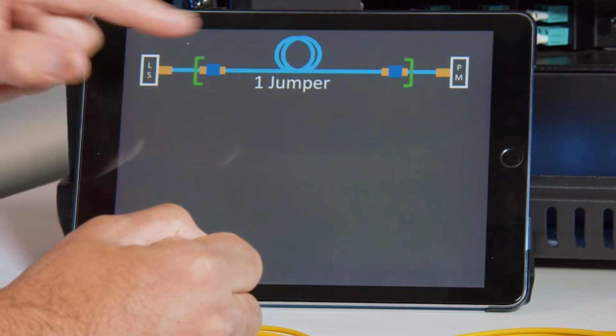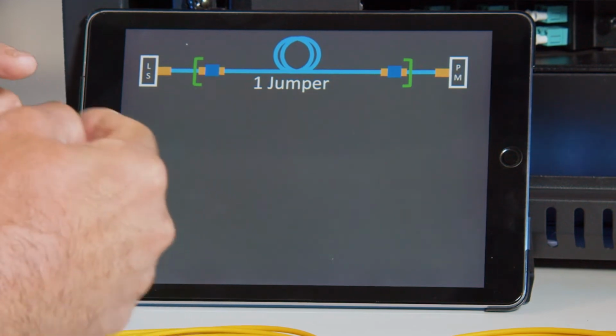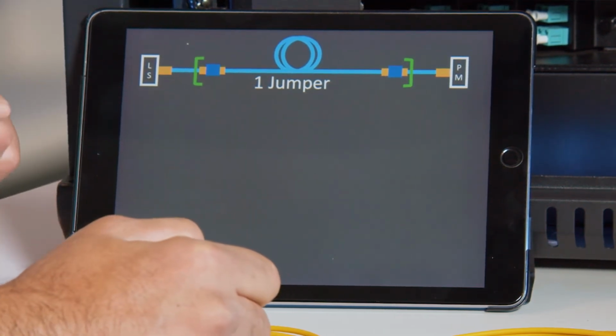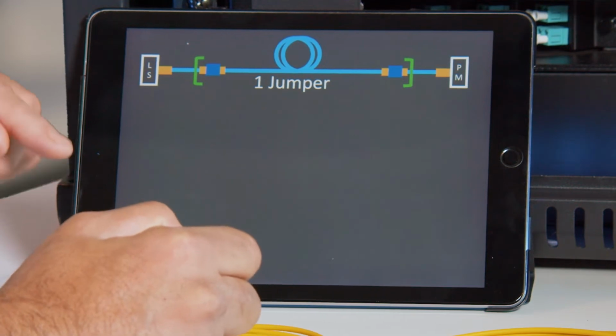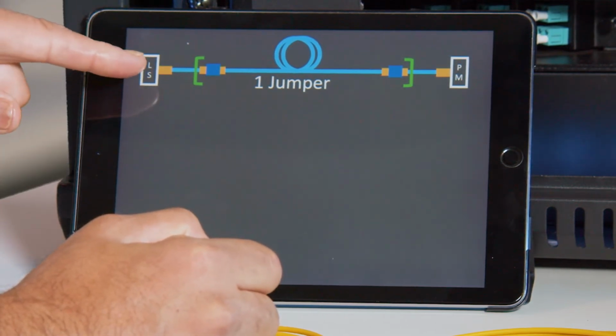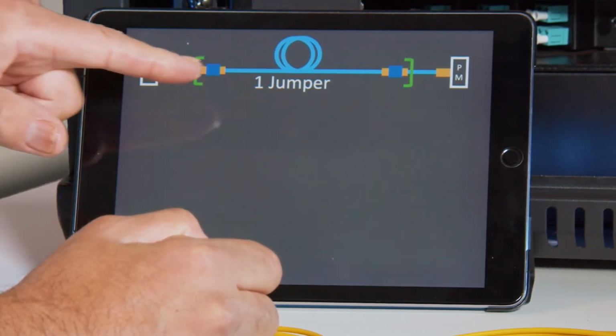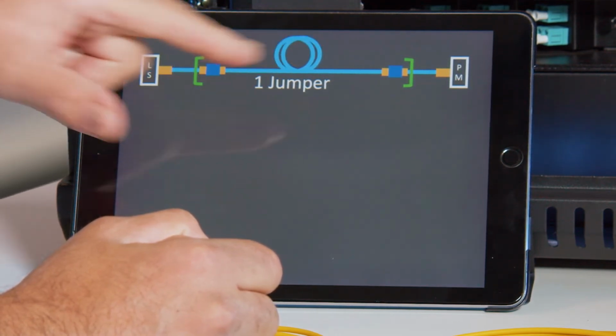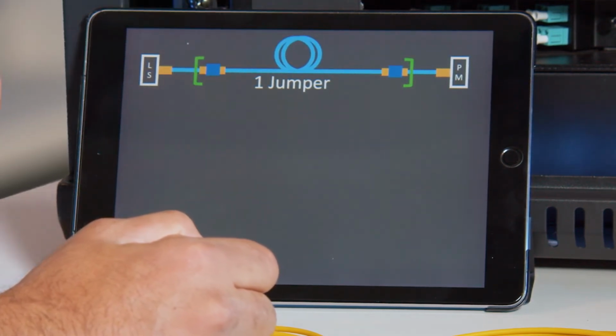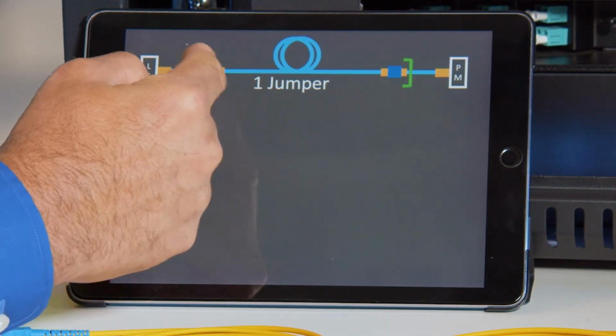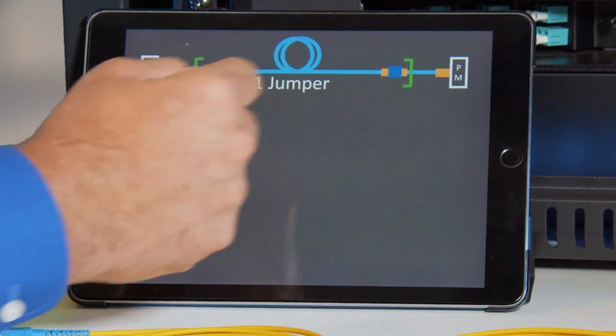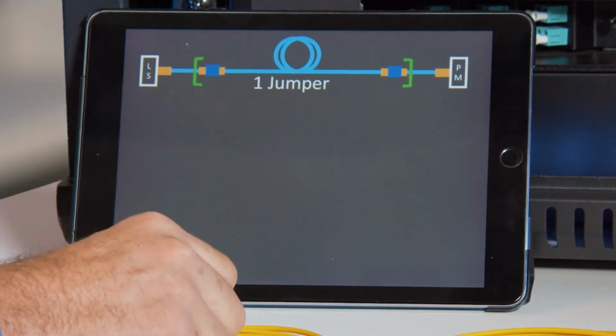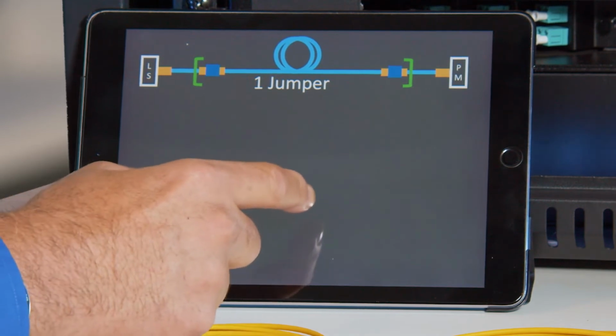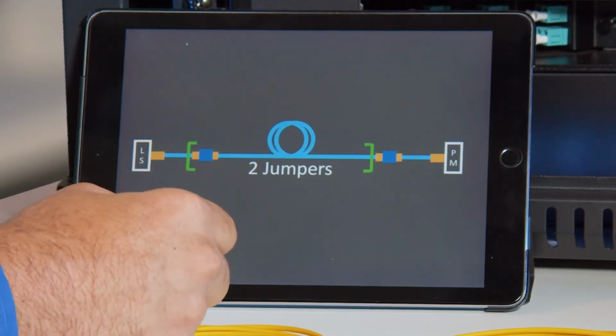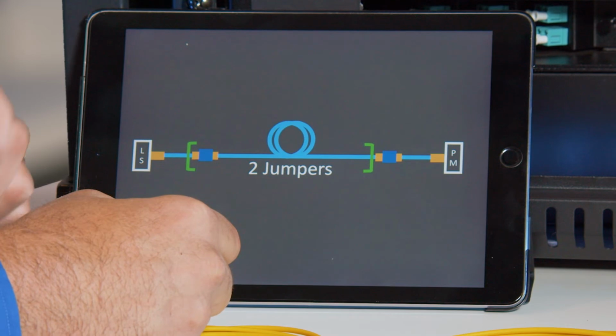So on the 1 jumper calibration system, this is where you're using 1 jumper to calibrate, and we'll look in more detail at how to do that in a later video. But when we use the 1 jumper calibration, what we measure is everything including the 2 couplers at each end and everything in the fiber in the middle. And there might be connectors or splices in that cable under test, but we're including the connector of the test jumper at each end when we do the 1 jumper calibration. So that's the preferred method because you're getting the most loss measurement.